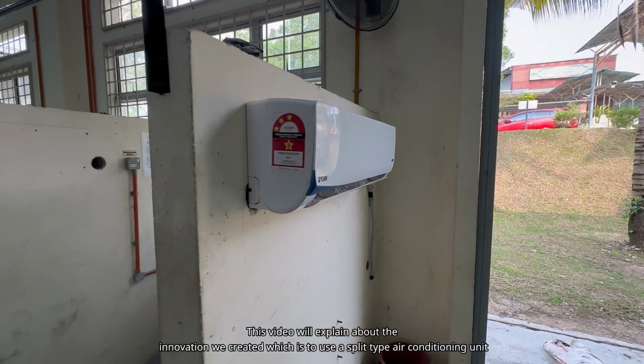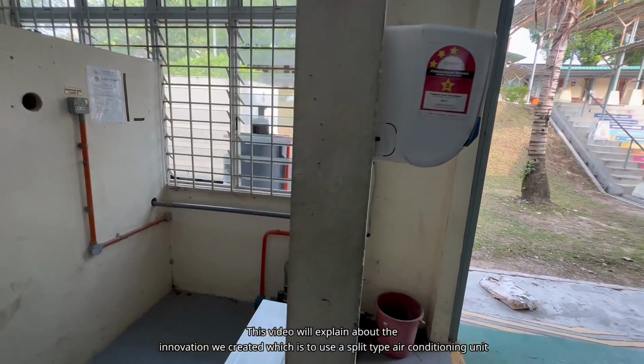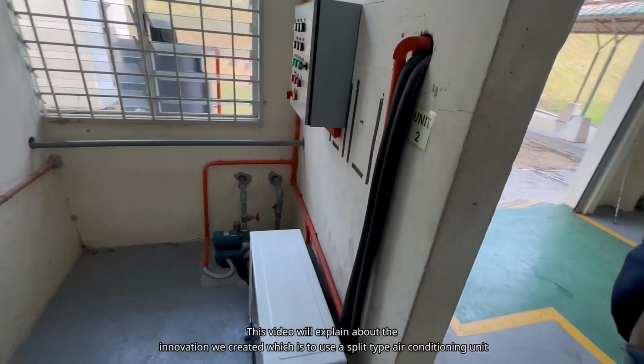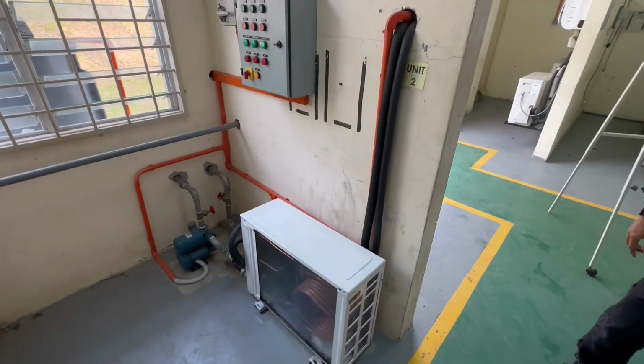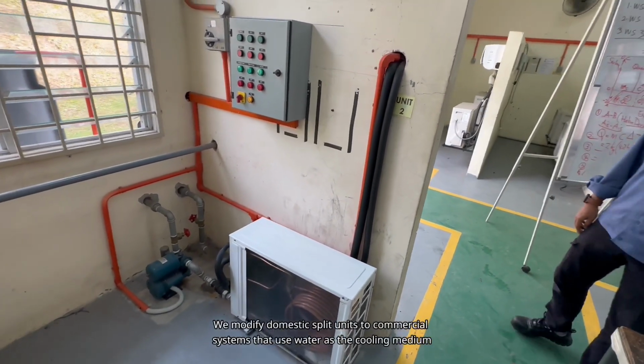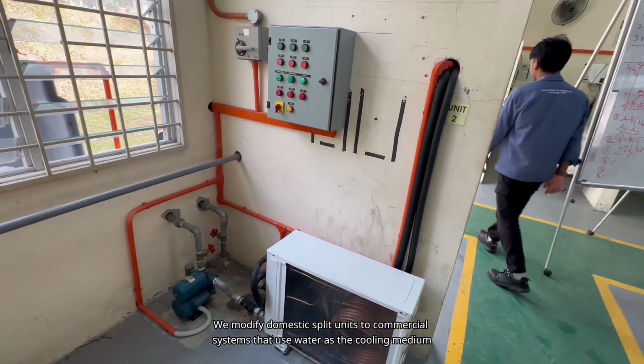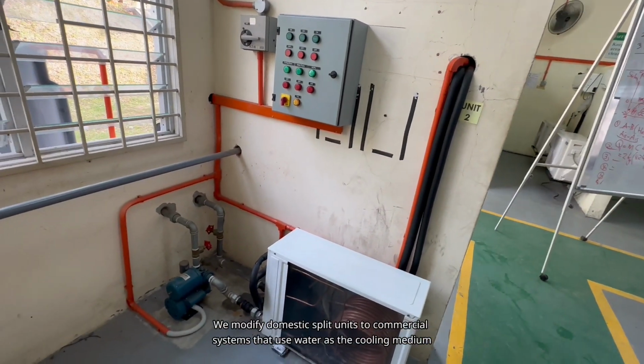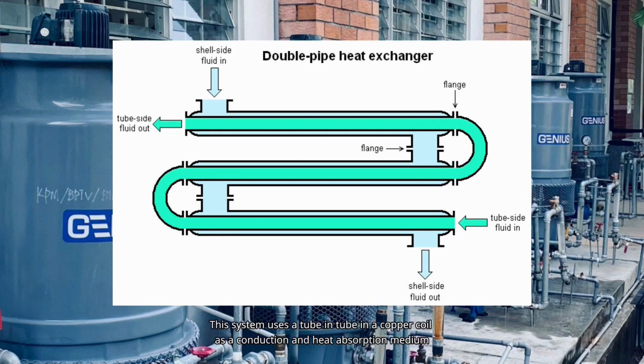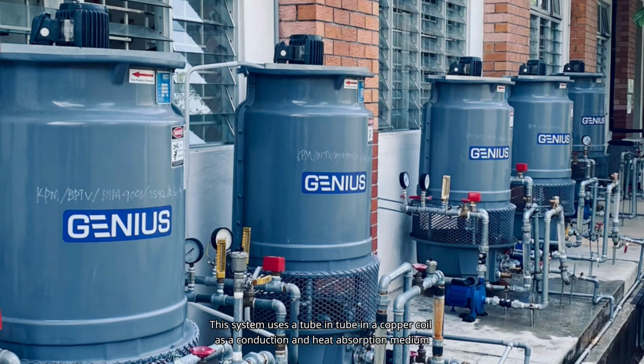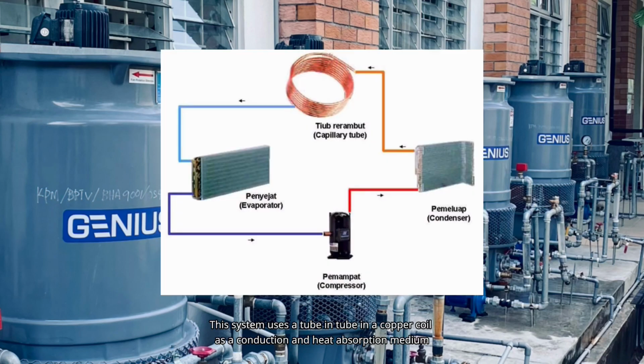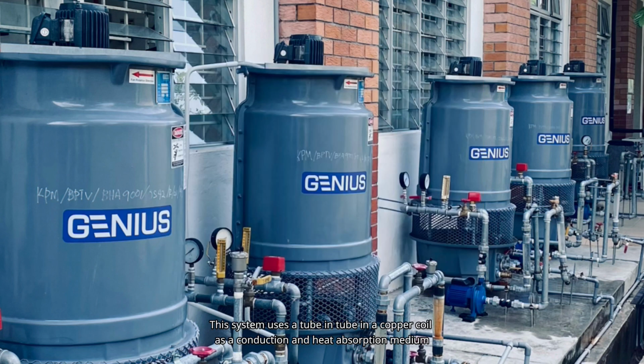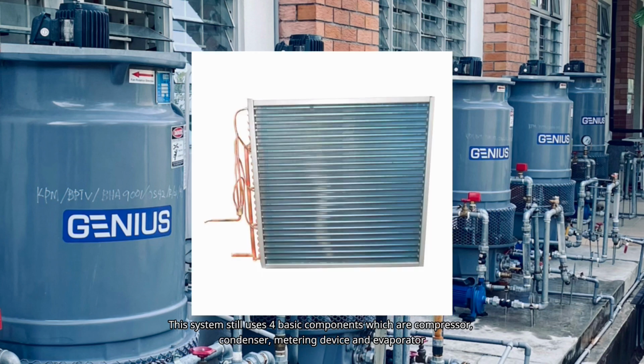This video will explain the innovation we created, which is to use a split type air conditioning unit. We modify domestic split units into a commercial system that uses water as the cooling medium. This system uses a tube-in-tube copper coil as a conduction and heat absorption medium, and it still uses the four basic components: compressor, condenser, metering device and evaporator.